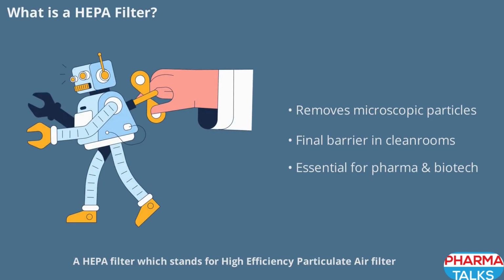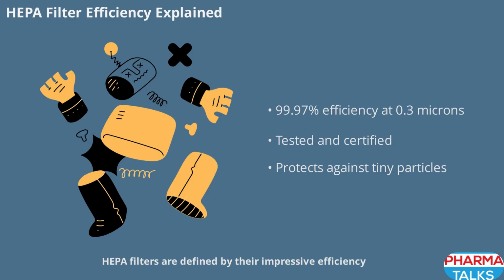control. HEPA filter, which stands for High Efficiency Particulate Air filter, is specifically engineered to remove microscopic airborne particles from the air. In cleanrooms, HEPA filters serve as the final barrier against contamination, making them indispensable in pharmaceutical manufacturing, biotechnology, and medical device production. Their primary role is to ensure that only ultra-clean air enters critical environments, protecting sensitive products and processes from harmful particles. HEPA filters are also commonly used in hospitals and laboratories, where maintaining air purity is essential for both safety and compliance.